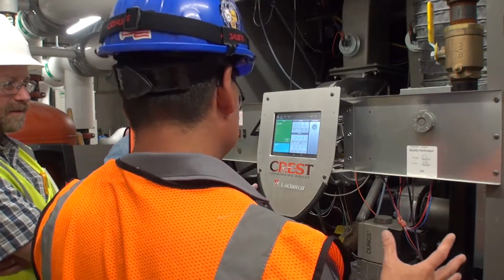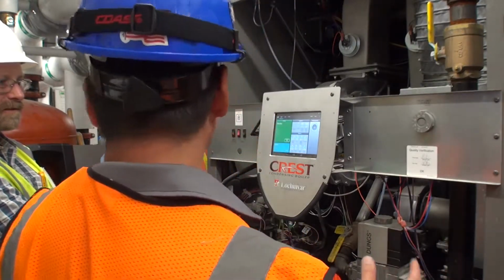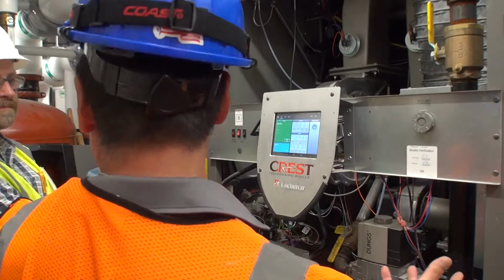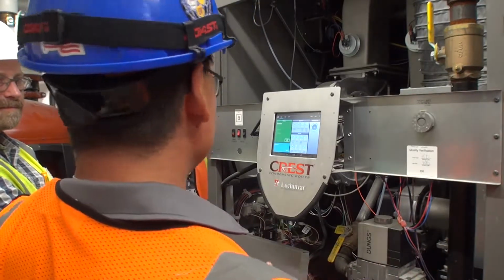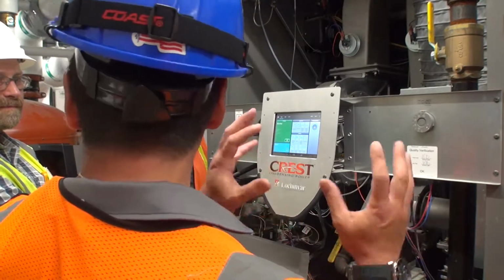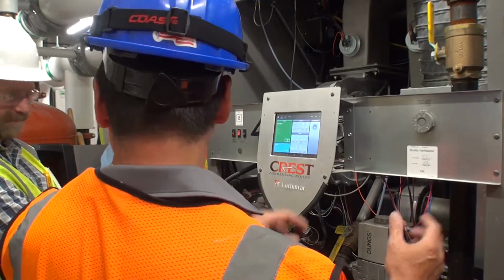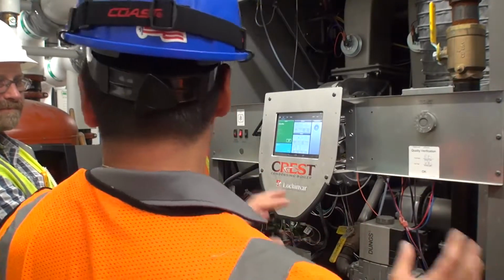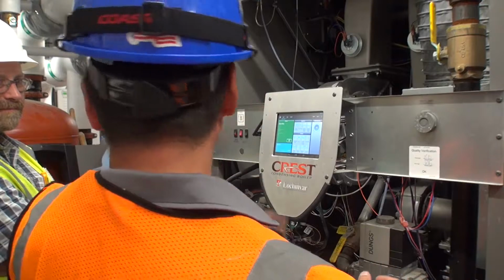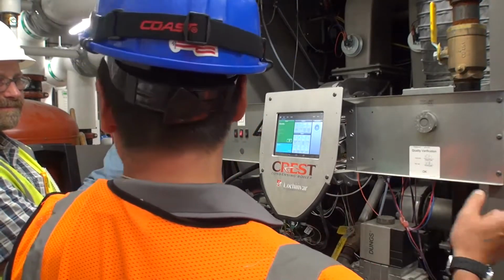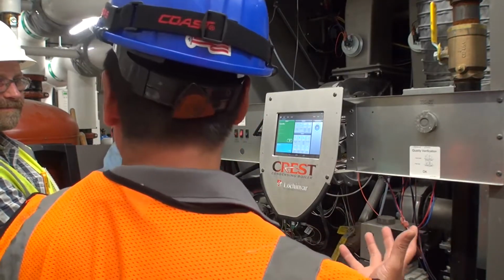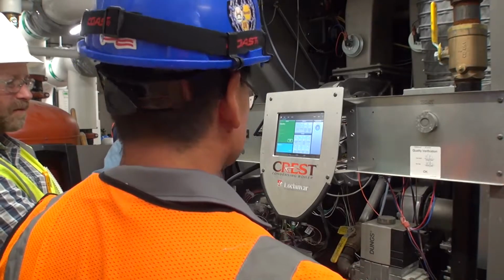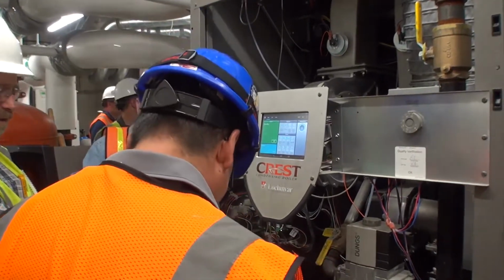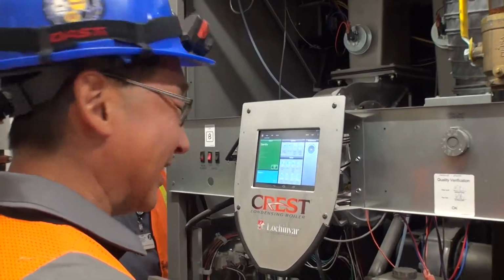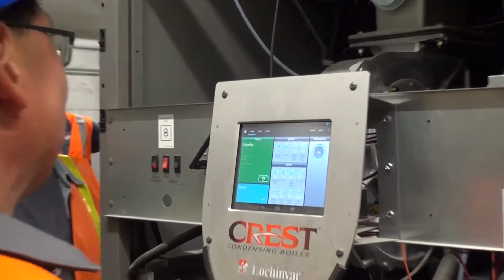So yeah, it wasn't the boiler's fault. The boiler was only showing the symptom of the valves lifting. It had nothing to do with over temp, over pressure, or the boilers themselves. They were not the problem. The valve lifted because it was doing its job. The system was overpressured and it had to relieve the pressure. Thank you for that explanation. That was a great explanation. Operator error, and a solution for it.